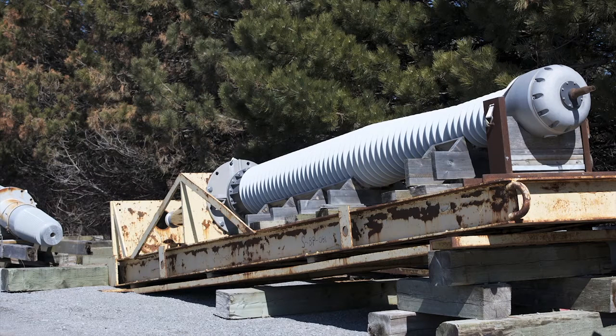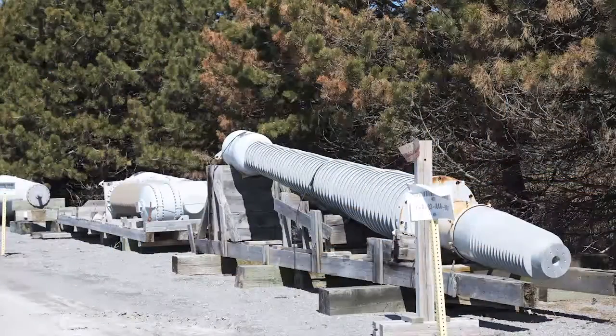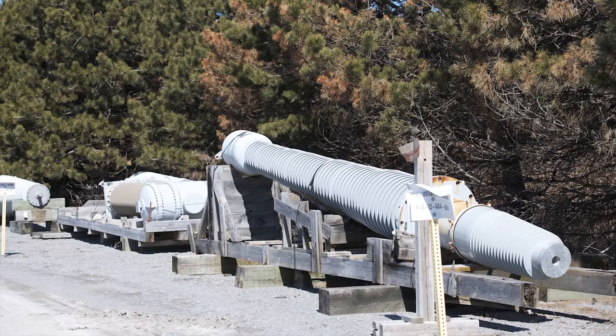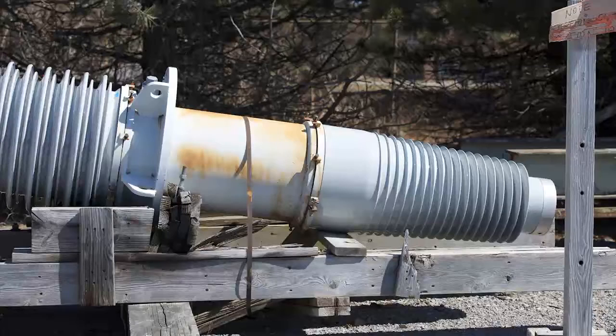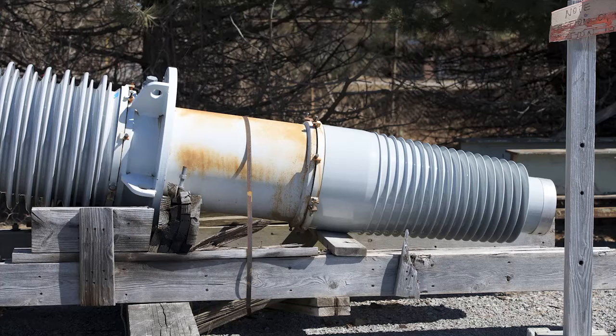Originally, the material used in the concentric cylinders wound around the conductor included resin-bonded paper as well as various carbon materials. Over the years, these were successively modified, leading to designs involving less conductive grades of plain paper along with aluminum foil. One of the major motivations behind the development of field-graded bushings was reducing the diameters required of the external porcelain shells. On ungraded bushings, the electric field tends to be concentrated around the flanges. Therefore, the risk of electrical breakdown becomes relatively high.